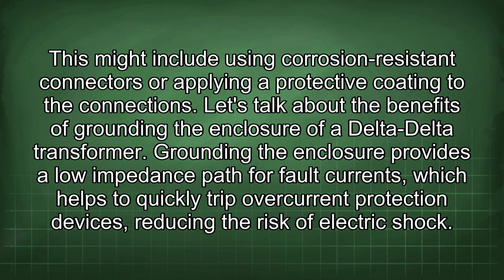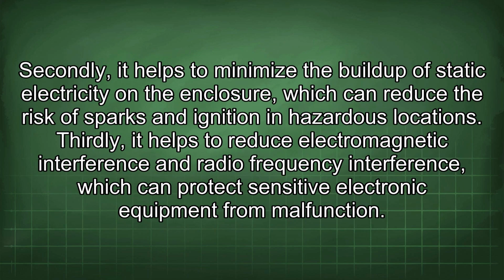Let's talk about the benefits of grounding the enclosure of a delta-delta transformer. Grounding the enclosure provides a low impedance path for fault currents, which helps to quickly trip overcurrent protection devices, reducing the risk of electric shock. Secondly, it helps to minimize the buildup of static electricity in the enclosure, which can reduce the risk of sparks and ignition in hazardous locations.